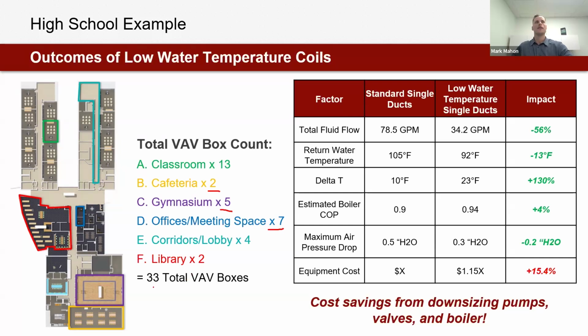The list goes on. For these 33 total VAV boxes, we see a 56% decrease in GPM on design day. We see a 13-degree reduction in return water temperature, which we would estimate, just looking at some standard boiler efficiency curves, this improvement in delta T actually yields 4% better boiler coefficient of performance. We're seeing a reduced maximum air pressure drop and an equipment first cost of about 15% higher.